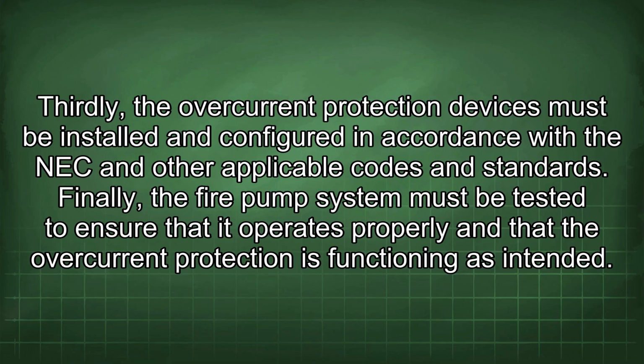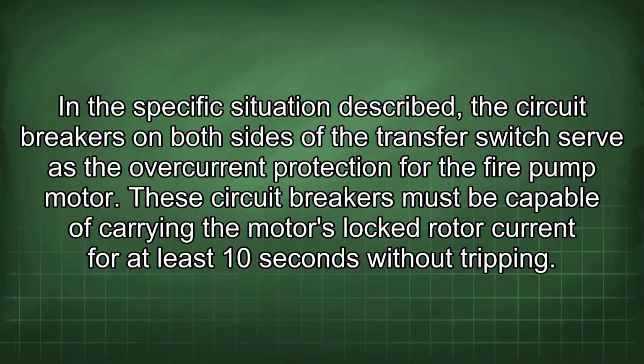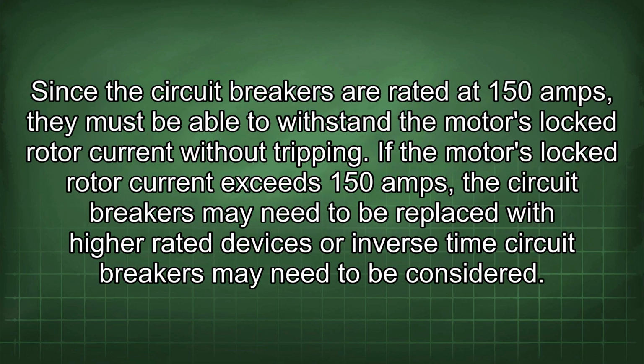Finally, the fire pump system must be tested to ensure that it operates properly and that the overcurrent protection is functioning as intended. In this specific situation described, the circuit breakers on both sides of the transfer switch serve as the overcurrent protection for the fire pump motor. These circuit breakers must be capable of carrying the motor's locked rotor current for at least 10 seconds without tripping. Since the circuit breakers are rated at 150 amps, they must be able to withstand the motor's locked rotor current without tripping. If the motor's locked rotor current exceeds 150 amps, the circuit breakers may need to be replaced with higher rated devices, or inverse time circuit breakers may need to be considered.